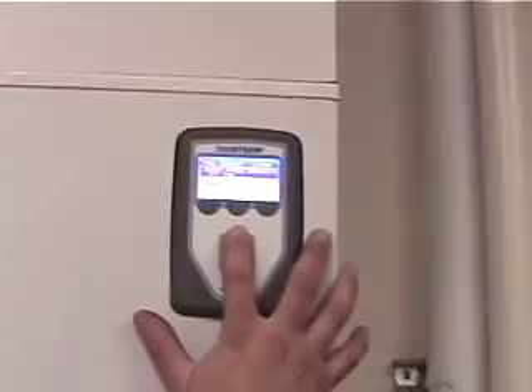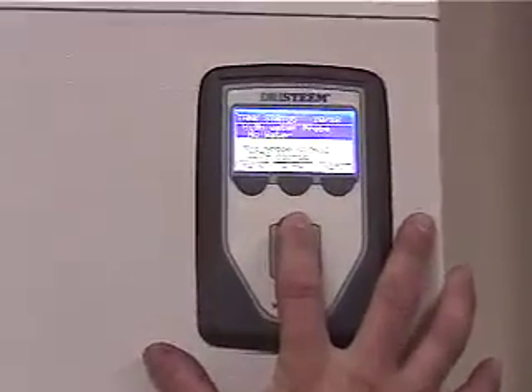So your humidity level is going to be different depending on what they're putting in. Oh yeah, you bring a pallet of paper in a room, it'll drop humidity like you've never seen. It'll absorb so much. Standard set point, like 35%. It was set for 35 when we got here. Yep.